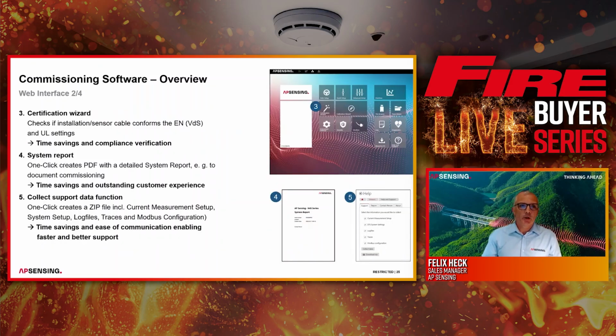The certification wizard is also on board of this commissioning software, where we check the sensor cable and adjust the parameters of the EN and UL settings, for example. This is a very practical approach to install and adjust the system in the correct way. Further to this, we have the system report for the documentation, and also if help is needed or if we should finally check the adjustments of the sensor, then we can use the support data function, and our support team can then help with the right adjustments of the controller.